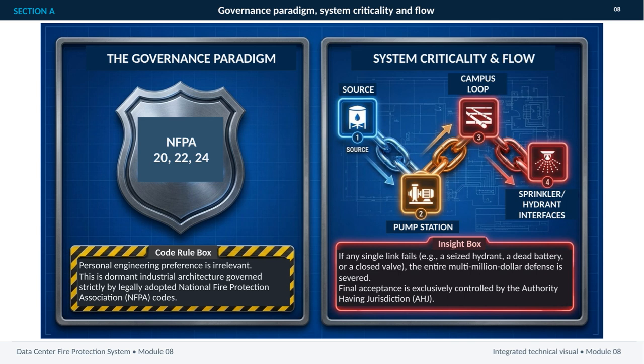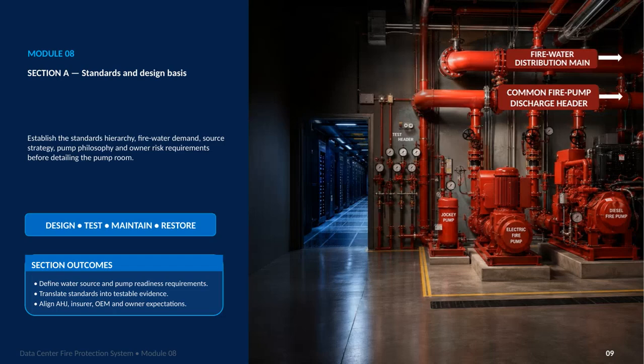That connection also creates the system's criticality. A seized hydrant, a dead battery, or a closed valve can interrupt a single link and sever the protection provided by the entire multi-million-dollar network. So final acceptance does not rest with the designer or operator. It is controlled exclusively by the authority having jurisdiction, or AHJ, which verifies that the installed system meets the adopted code requirements. This module begins with the design basis for a data center fire protection system.